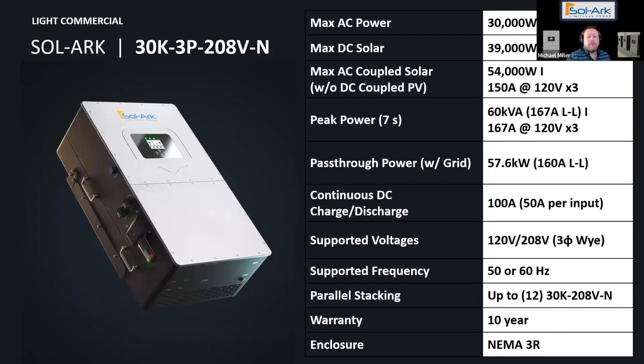Our battery inputs, there's 2 battery inputs per inverter, 50 amps each, so we get 100 amps. And you'll see that if you have 100 amps and you're running that at around a 300 volt battery bank, that's where you get your 30,000 volts. Or sorry, 30,000 watts. This is a 208/120 inverter. And I'll show you the 60K in a second. That's going to be 480/277. So you won't need any transformers when you install these, if you're installing them to the voltage that is at the site.